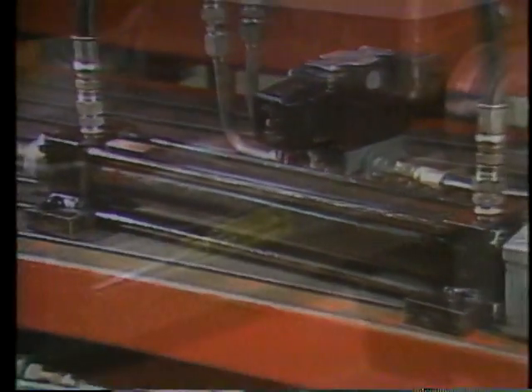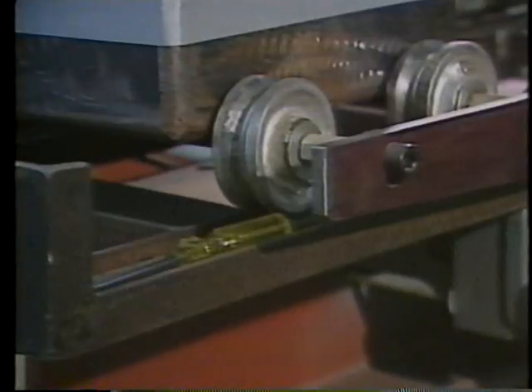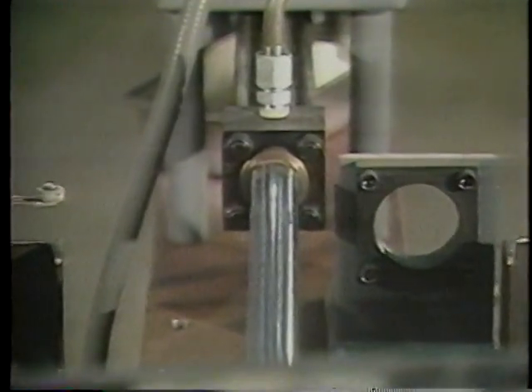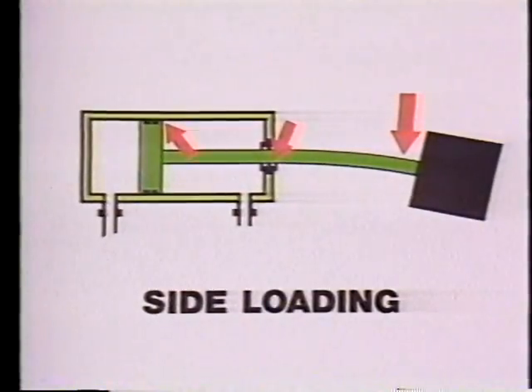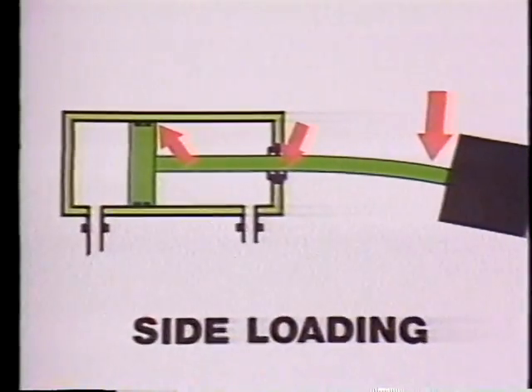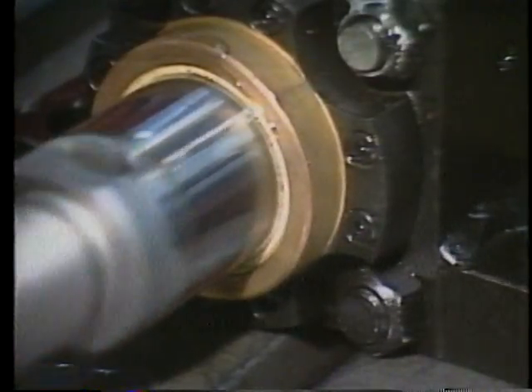What might be wrong at the cylinder that we can detect easily? One possibility is a mechanical failure. A system might be perfectly capable of providing the correct flow, but if the load is jammed, the normal force generated by the cylinder may not move it at all. Or if a cylinder body has been hit hard and is restraining the piston, fluid flow will also be impossible — so check the cylinder body for obvious signs of damage. A similar problem occurs if the rod has been bent or the cylinder and load have become misaligned, causing side loading.